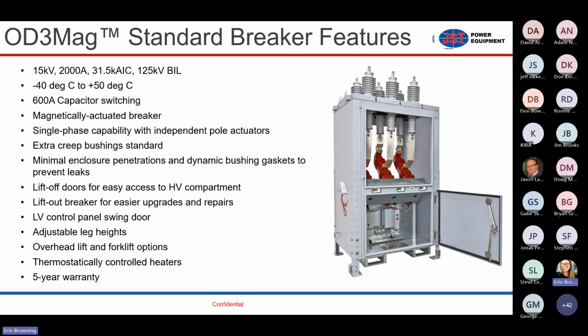The temperature ratings are from minus 40 degrees C to 50 degrees C, and the capacitor switching is rated for 600 amps. Again, this is a magnetically actuated circuit breaker. There's not a lot going on in this low voltage cabinet. Down here, what you see is a control board that's responsible for driving the vacuum interrupters open and closed. Otherwise, there's not really anything that needs to be touched or serviced inside of this cabinet.